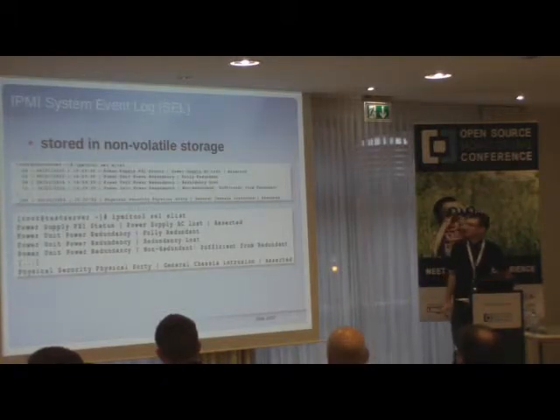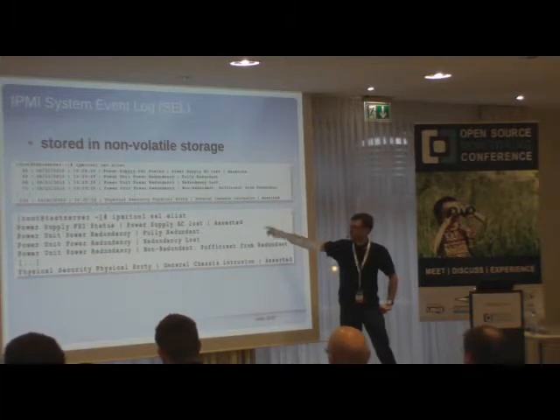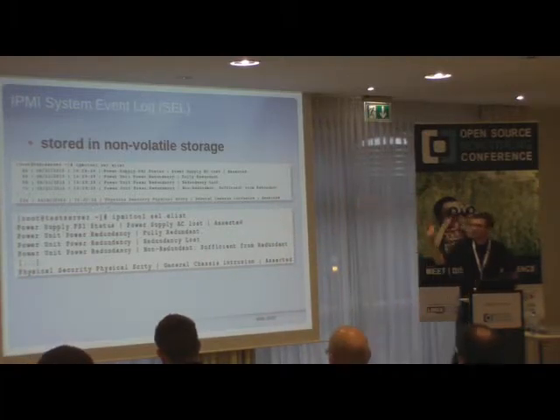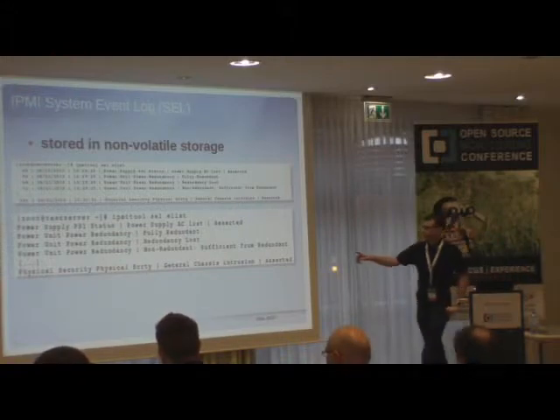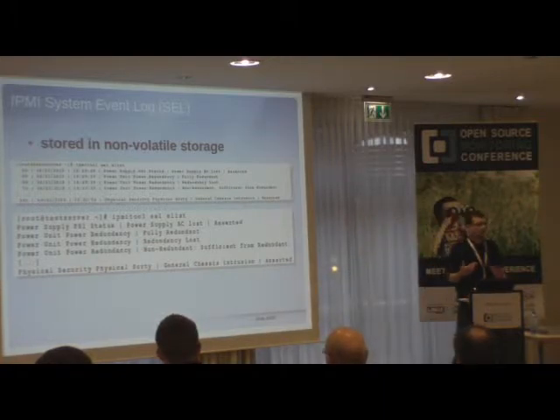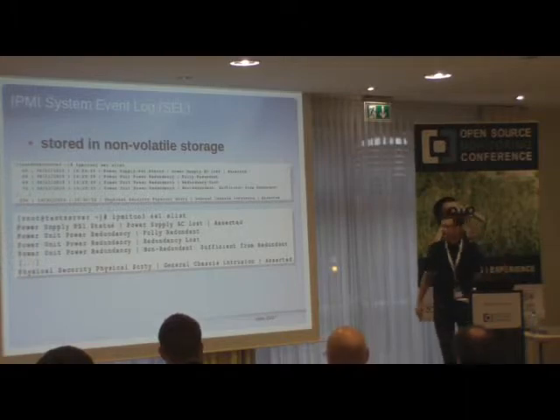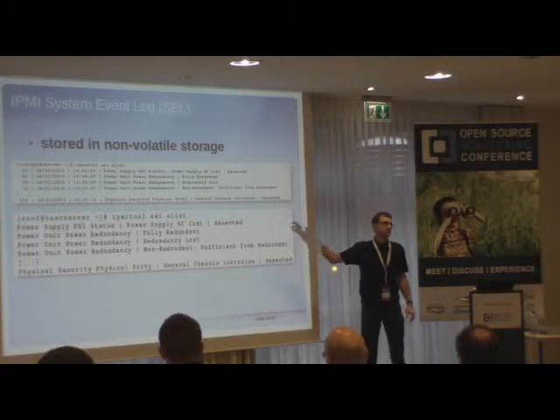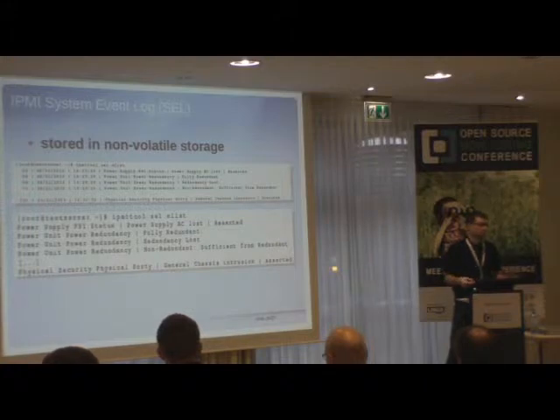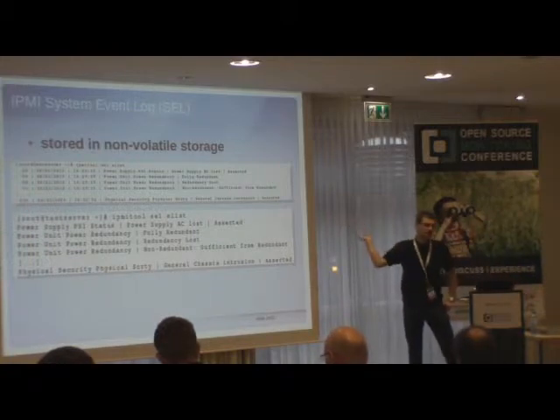You also have this kind of error log — the system event log, or SEL. Here you get information like whether power redundancy has been lost. You can use tools like ipmitool or the free IPMI suite to get this information. An important hint: depending on your server, you can get a lot of messages when you boot the server or do kernel updates. The log holds about 10,000 lines, so it can fill up. When it's full, no additional information gets logged, so it's a good idea to check it, save the output to a file, and then clear it.